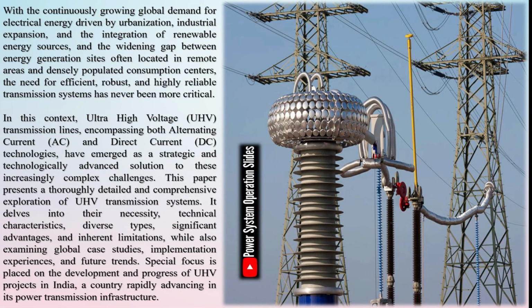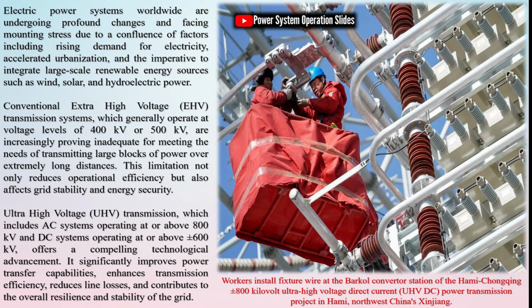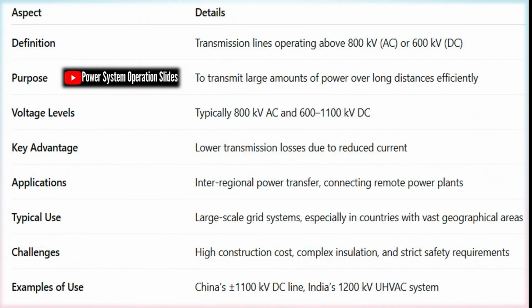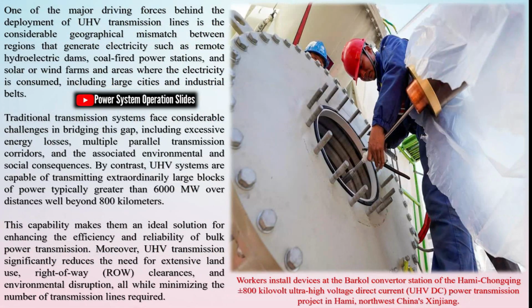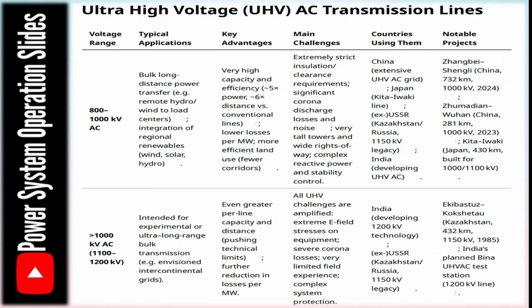Ultra-high voltage (UHV) transmission lines are power lines designed to carry electricity at extremely high voltages, typically above 800 kV AC or 600 kV DC. These lines are used to transmit large amounts of electrical power over long distances with minimal losses. By using higher voltages, UHV systems reduce the current for a given power level, which decreases resistance losses and improves efficiency. They are crucial for connecting remote power generation sources, like hydro or renewable plants, to urban or industrial centers, ensuring reliable and stable power supply across vast regions.